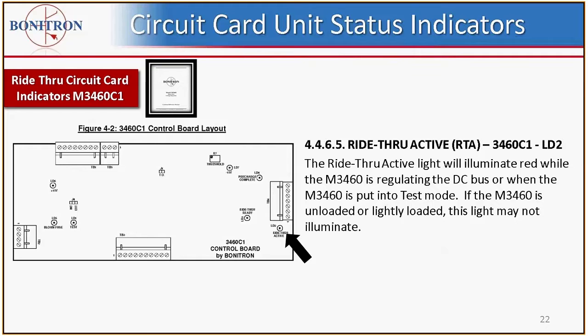Then we have the ride-through active light, also on the C1 board. The ride-through active light illuminates red while the M3460 is regulating the DC bus, or when the 3460 is put into test mode. If the 3460 is unloaded or lightly loaded, this light may not illuminate. It looks at the difference of the boosting of the DC bus, and it tells you that the ride-through is actually boosting into the DC bus. What we sometimes run into is that the light may not indicate, because when you do a ride-through test, if the DC bus level is already high, close to the overvoltage trip, it will not allow it to boost to an overvoltage fault.